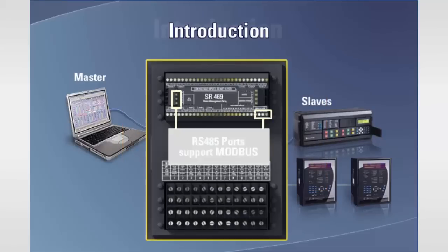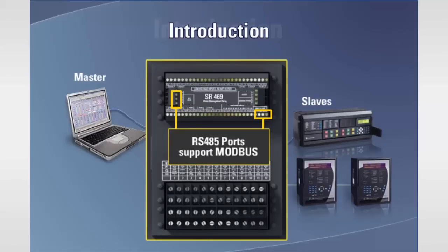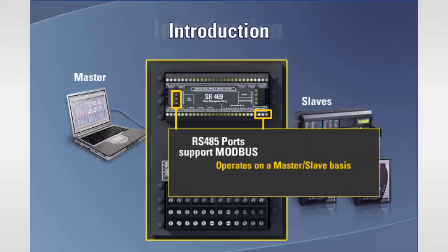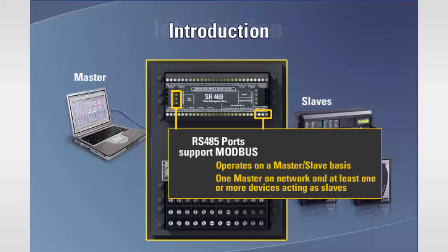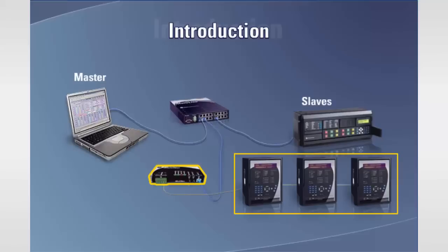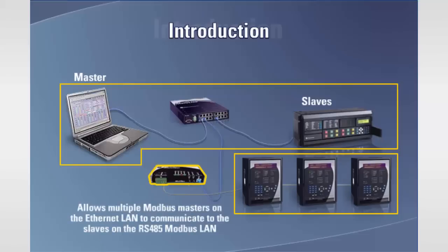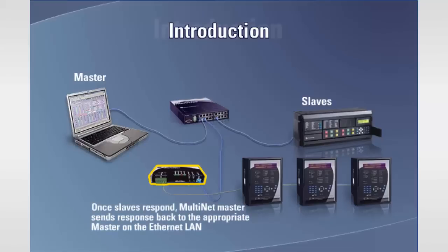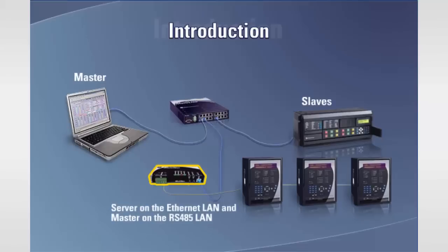The GE Multilin RS-485 ports support a protocol called Modbus, which we will discuss in detail later in the course. The Modbus protocol is like a language and operates on a master and slave basis. Within the implementation of Modbus, there is only one master on the network and at least one or more devices acting as slaves. The master initiates all communications. The GE Multilin Multinet Serial to Ethernet Converter is a communications module that interfaces an RS-485 Modbus LAN to an Ethernet LAN. This allows multiple Modbus masters on the Ethernet LAN to communicate to the slaves on the RS-485 Modbus LAN. The Multinet does this by buffering the commands sent by the masters and then acting as the master on the RS-485 LAN. The Multinet acts as a server on the Ethernet LAN and a master on the RS-485 LAN.